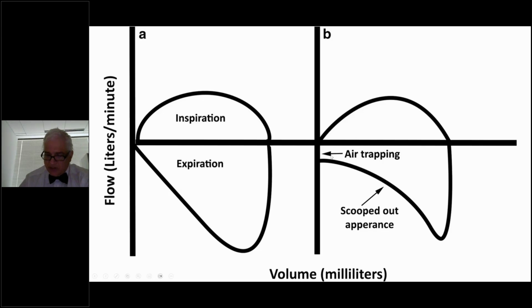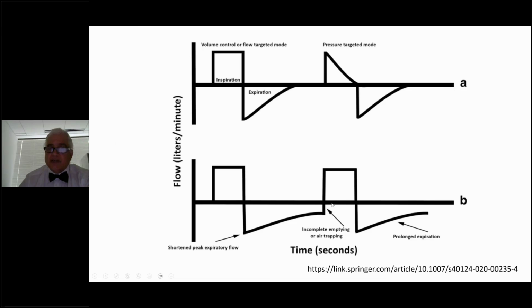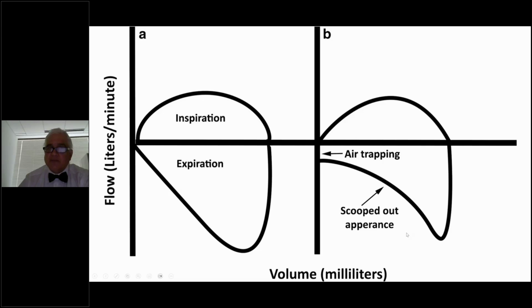So when you see these two instances, first on the scalar, where it doesn't get back to the baseline, and second, where you see on the flow volume loops, this scooped out appearance in expiration, where you don't quite touch or where you don't quite connect to your inspiration, that also can indicate trouble with emptying and can result in significant gas trapping and result in issues with volume delivery.